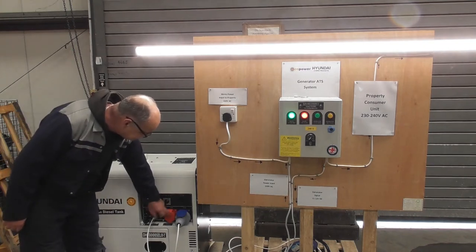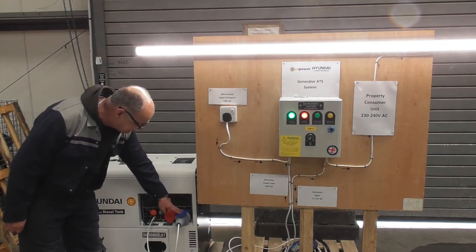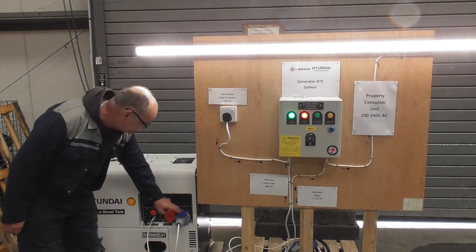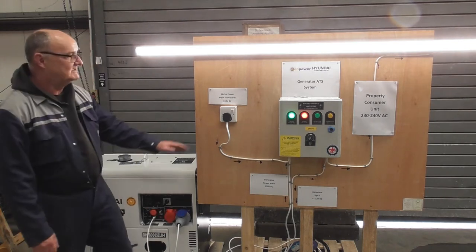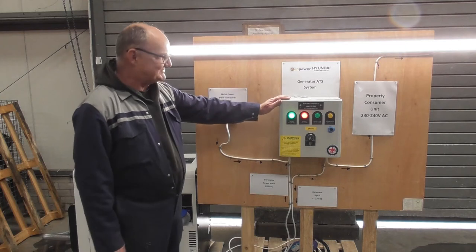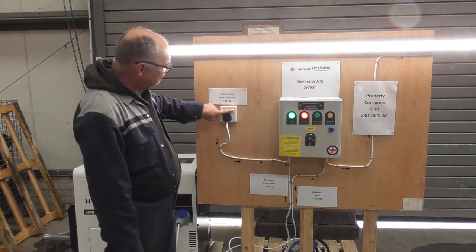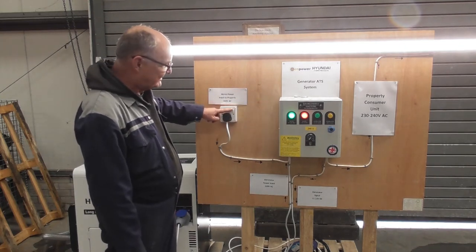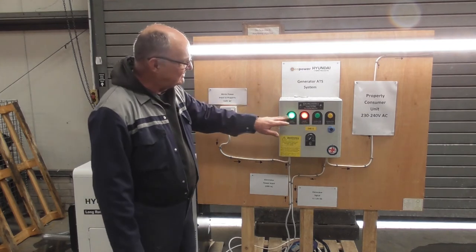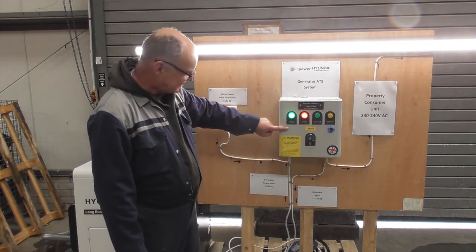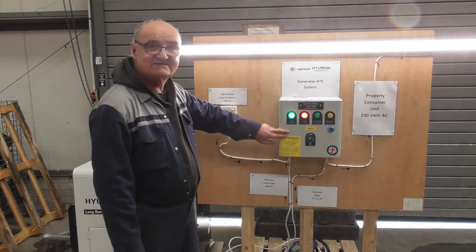The T stands for three phase but it also has single phase. For this demonstration I'm using the single phase as opposed to the three phase. So what's going to happen is I'm going to simulate mains failure by turning off this switch. Both of these lights will go out and a signal will come from this box to the generator asking it to start.